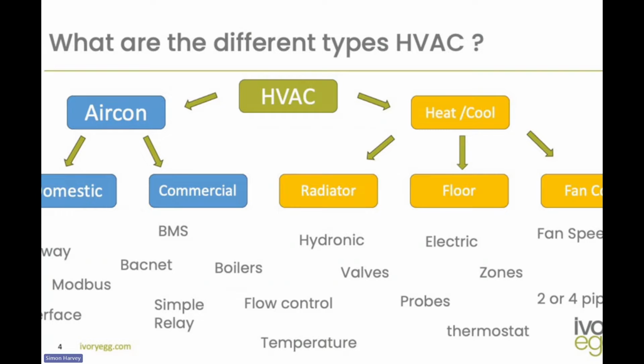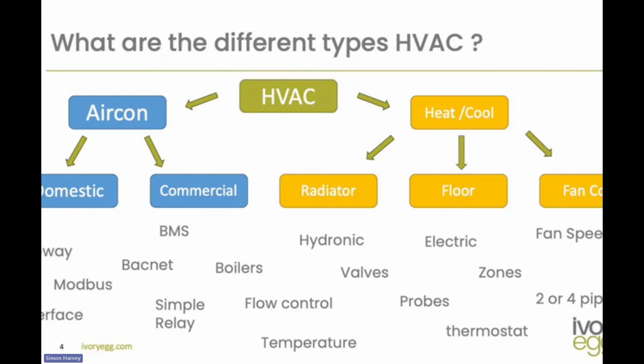In domestic and commercial air conditioning, we look at things like gateways, which are system-to-system protocol translators. Generally we'll see an air conditioning gateway talking to a KNX to air conditioning gateway. Interfaces are more one-to-one, controlling just an indoor unit, and that could present itself as Modbus as well. In the commercial space, we see a lot of BMS, BACnet, and simple relay control, which is just a relay to turn on the heating and cooling.